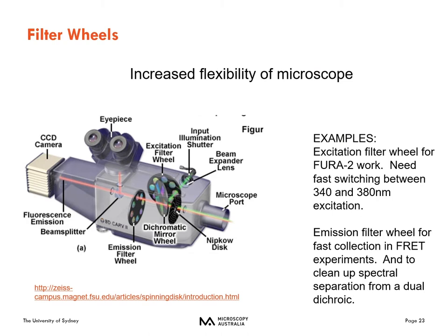For really fancy filter arrangements, you can use filter wheels — excitation, dichromatic mirror, or emission filter wheels, or some combination — to enable fast switching. This gives you nice spectral separation while still collecting images fairly quickly in time. For example, an excitation filter wheel is useful for FURA-2 work requiring fast switching between 340 and 380 nm, while an emission filter wheel is useful for FRET experiments or cleaning up spectral separation when imaging live cells.